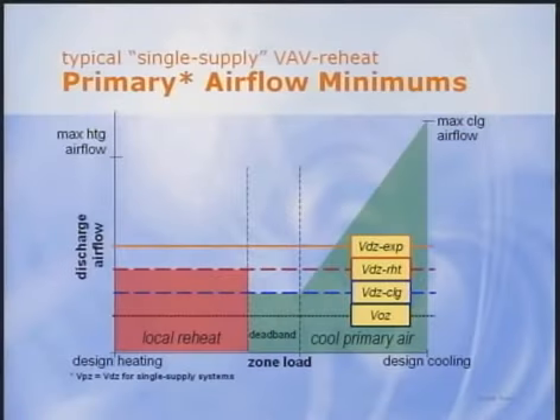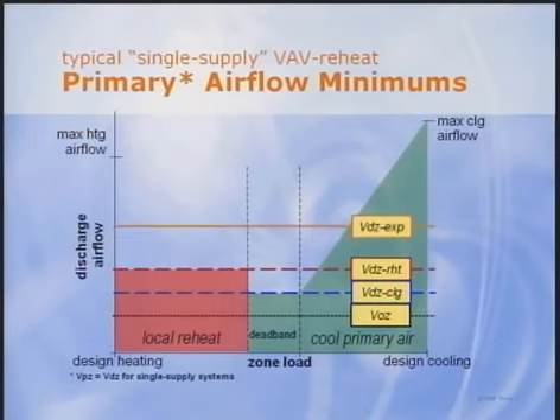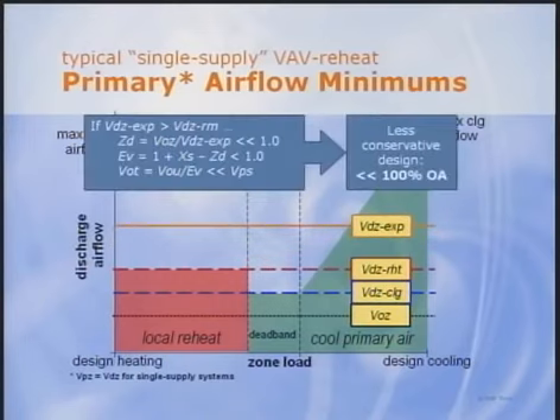If the reheat minimum setting allowed by Standard 90.1 is too close to the minimum outdoor air required by Standard 62, the outdoor air fraction may be close to 1. This probably doesn't happen in office buildings, but it can happen in schools. Designers who don't want to be as conservative might use a building performance analysis to determine the highest outdoor air intake flow at any load. Then use the discharge airflow at each zone at this hour as the minimum expected value at the condition analyzed.